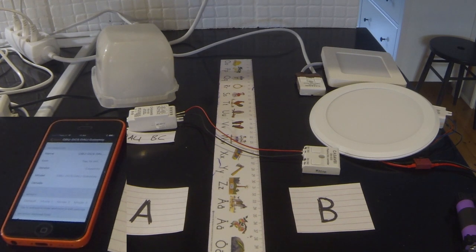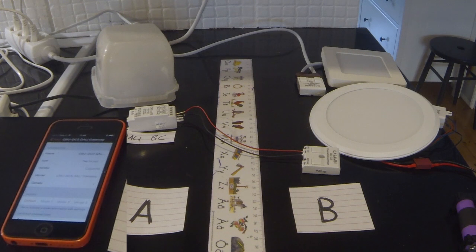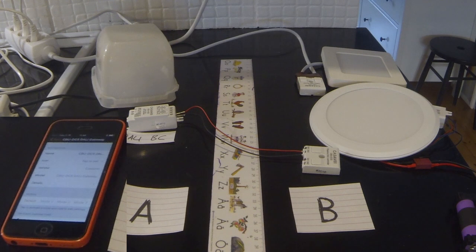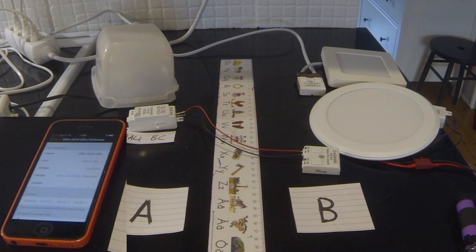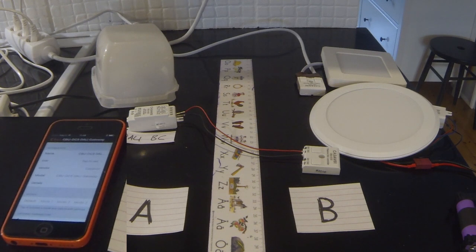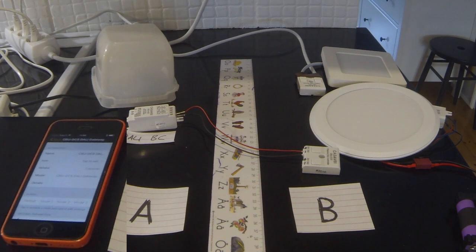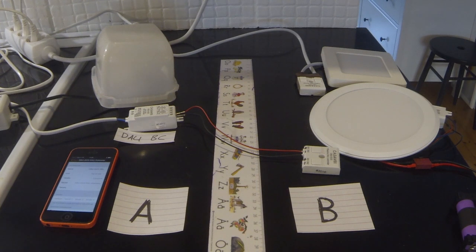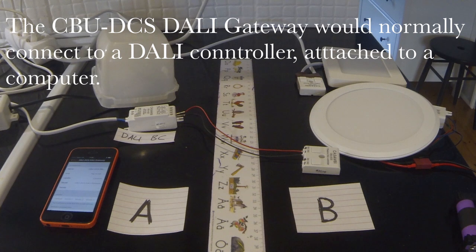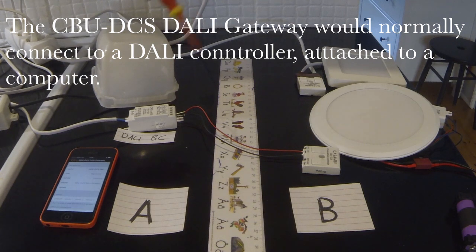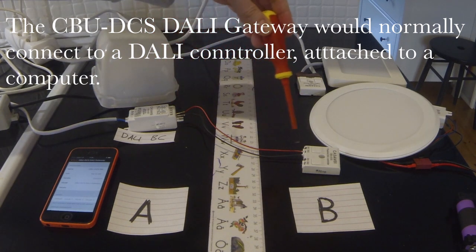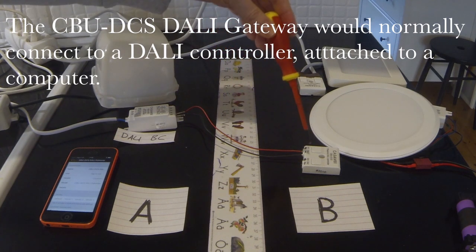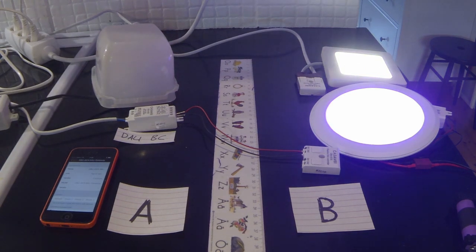So as you know, the CBU-DCS is not a new product at all. This DALI gateway that we're using now isn't actually a different physical product either. It's just a different fixture profile for the DCS. It's not new at all. I believe it came out close to two years ago, if I remember rightly. I've not talked about this in the past because it's really something that's just used for commercial environments. So this device here in gateway DALI gateway mode would, for example, allow you to extend a physically wired DALI network with some CASAMBI devices. Because what it does is it reads the DALI signal coming down these wires. It then translates it into CASAMBI's language and talks to the CASAMBI devices.